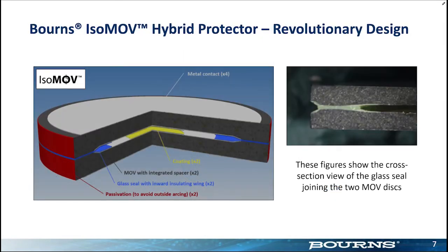And here's a blow-up of what's going on. There's metallized contacts on the top and bottom, similar to a normal MOV. But in between the MOVs is an evacuated space where the GDT gases are. They're sealed with glass on the circumference. And that yellow area inside is the electrodes for the GDT. That's the active GDT area. That's where the arcing and the firing of the gas occurs. On the right-hand side is a close-up of the glass seal that you can see there.